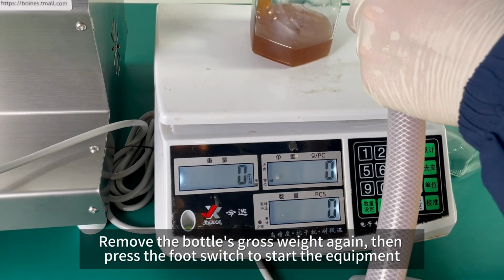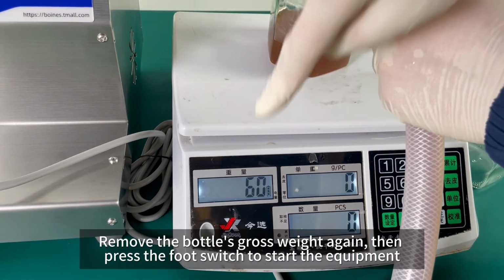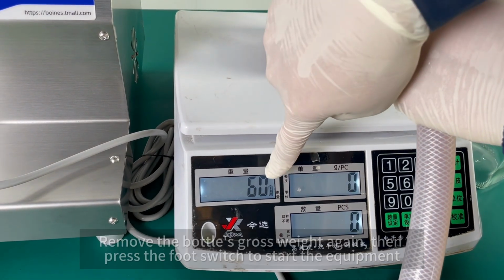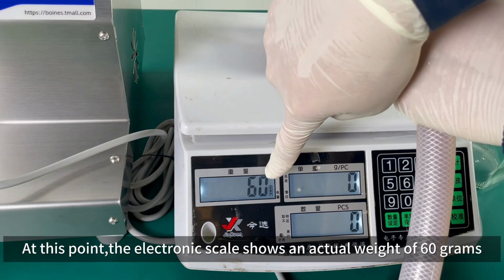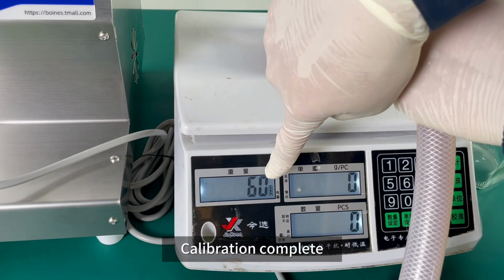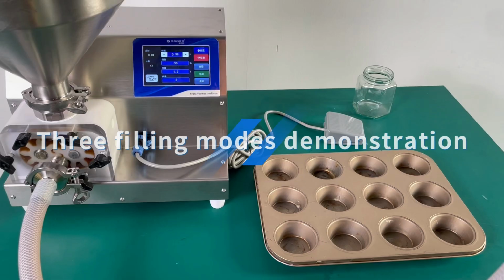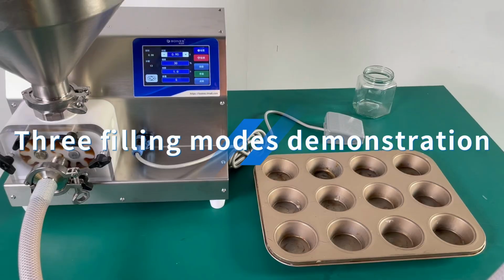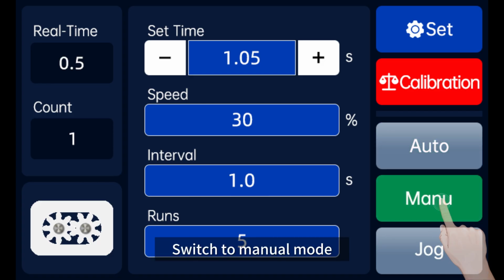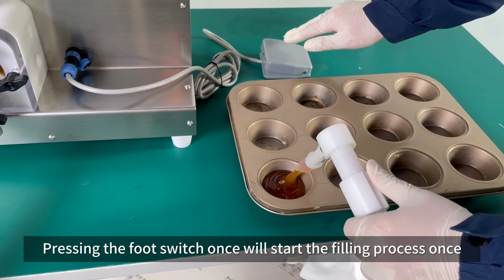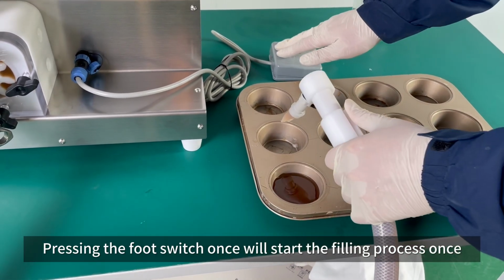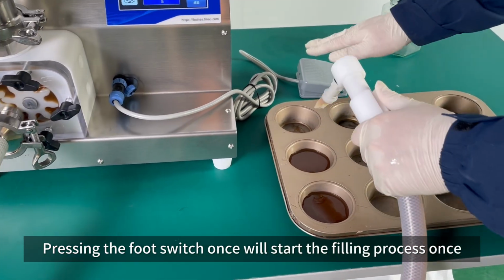Remove the bottle and weigh again, then press the foot switch to start the equipment. At this point, the electronic scale shows an actual weight of 60 grams. Calibration complete. 3 filling modes demonstration. Manual mode. Switch to manual mode. Pressing the foot switch once will start the filling process once.